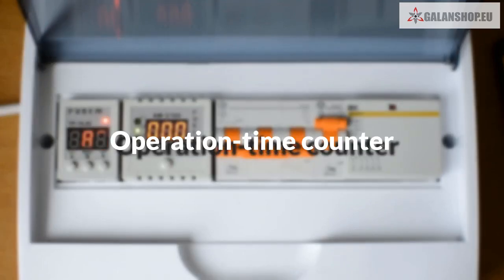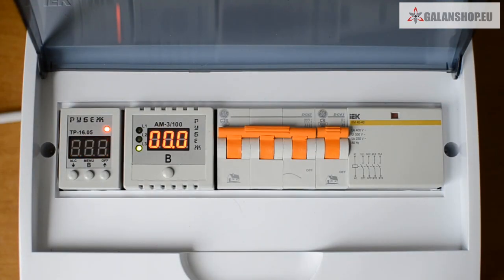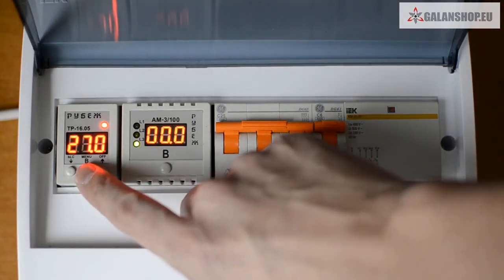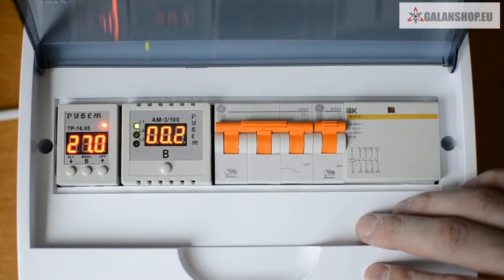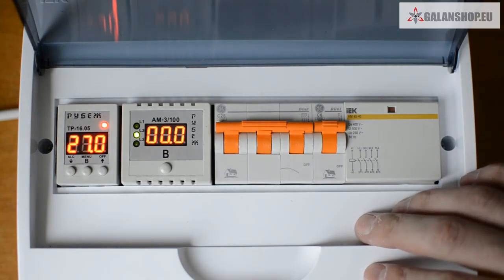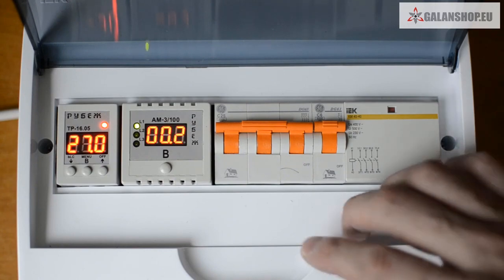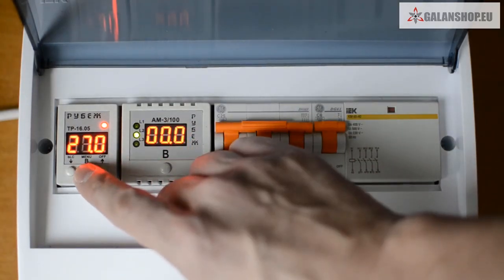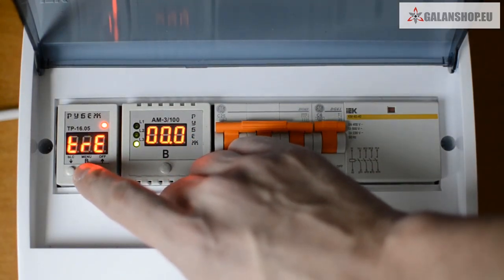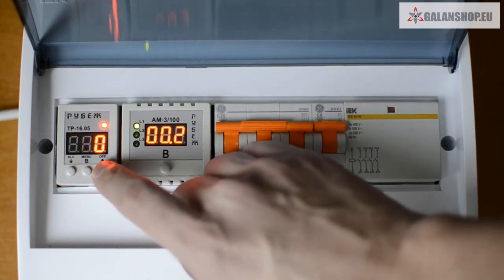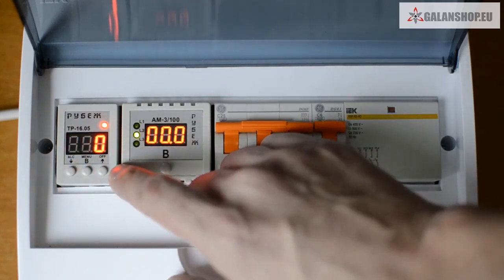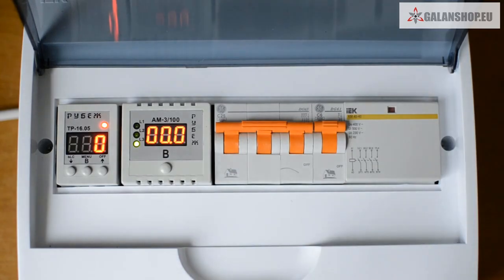Operation time counter. This model of heat controller has a built-in operation time counter. The time is calculated every second of the heat controller's operation and is saved in the device internal memory every 15 minutes. Even in case of a power cut, data is stored in memory. The calculated time is recorded in a heat controller's TRE menu in increments of 1 hour. A maximum recorded value is equal to 999 hours. When the maximum value is reached, the time count stops. You can resume counting by resetting the counter.